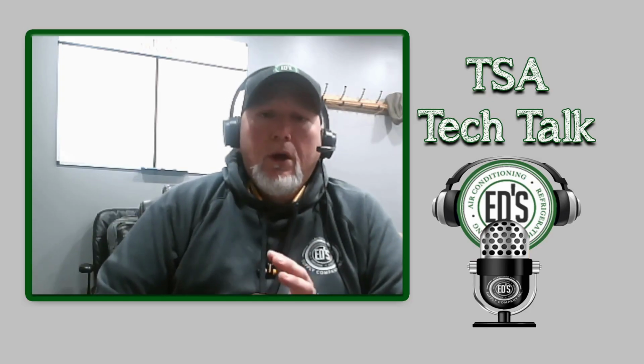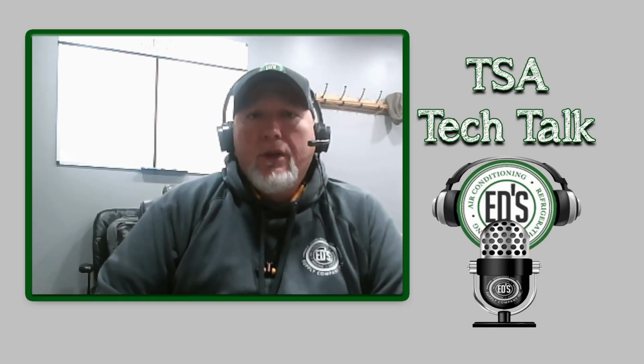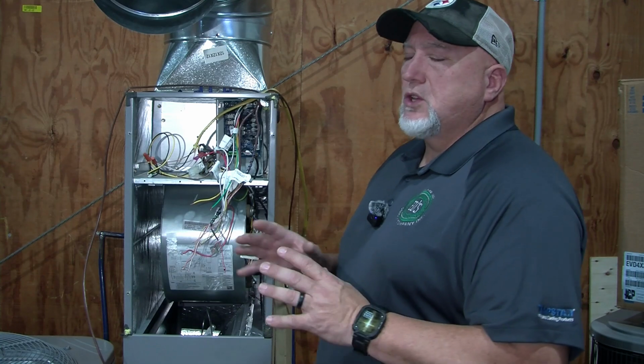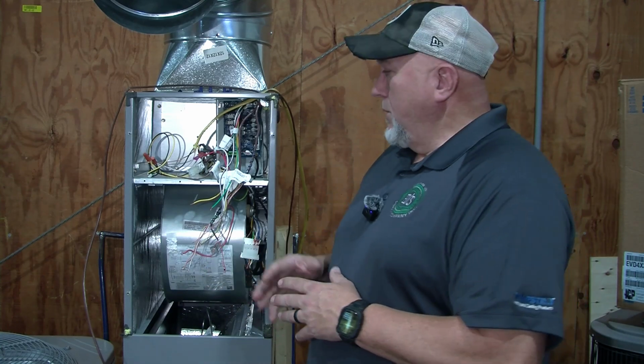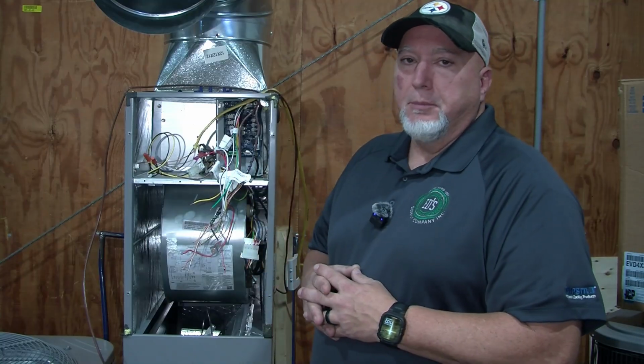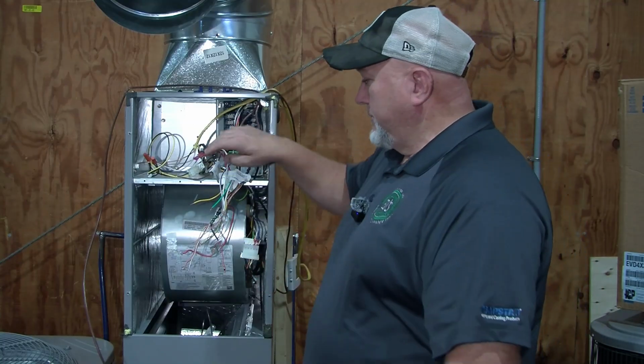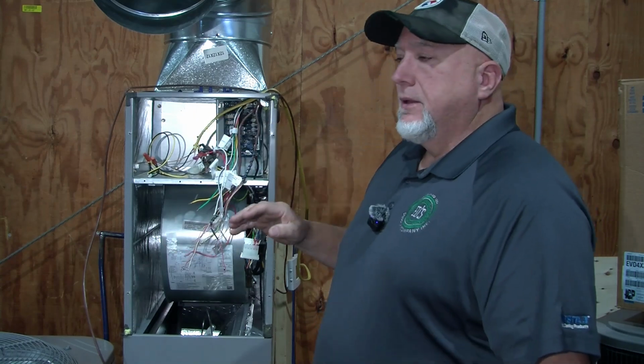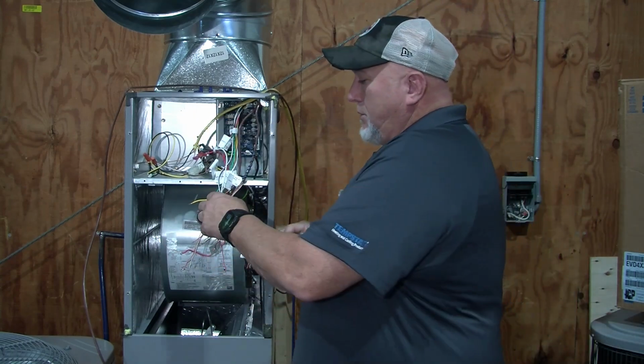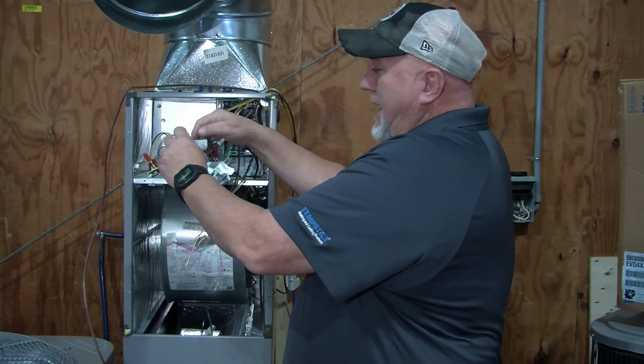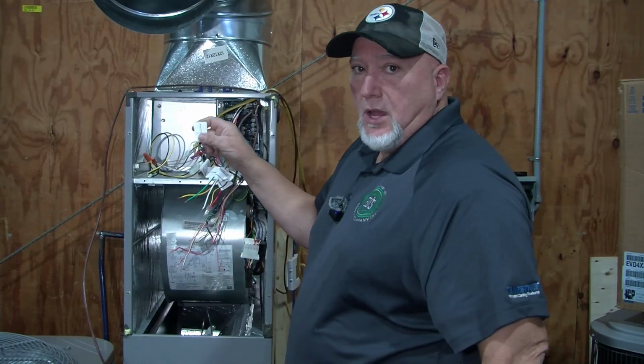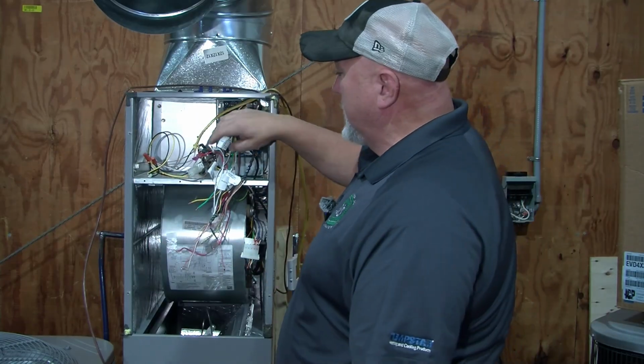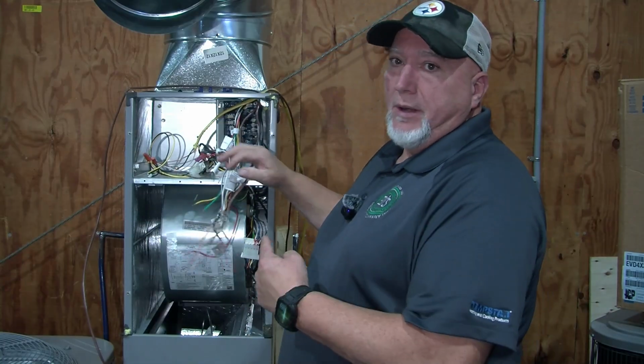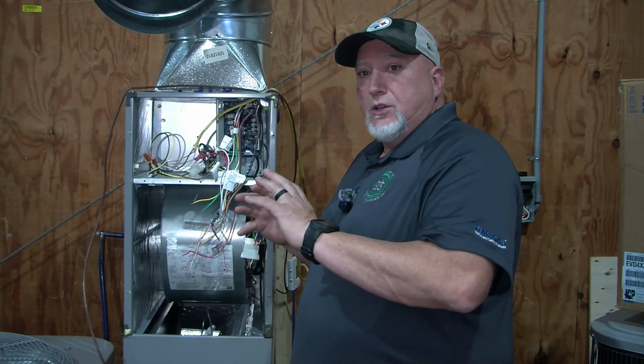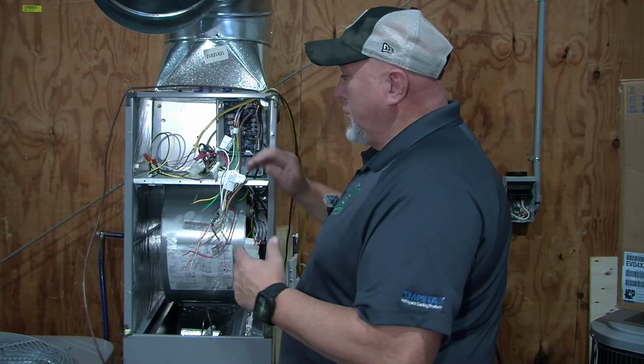We're going to show you out in the warehouse right now on the equipment hands-on. Most common things we run into is how do you properly wire up this air handler. So with ICP, just to explain a few things, they have these big labels on a piece of equipment and on the wires. We're going to go over exactly what label that is and where that wire goes, and then we'll show you exactly how to wire it up so that you don't have any issues.